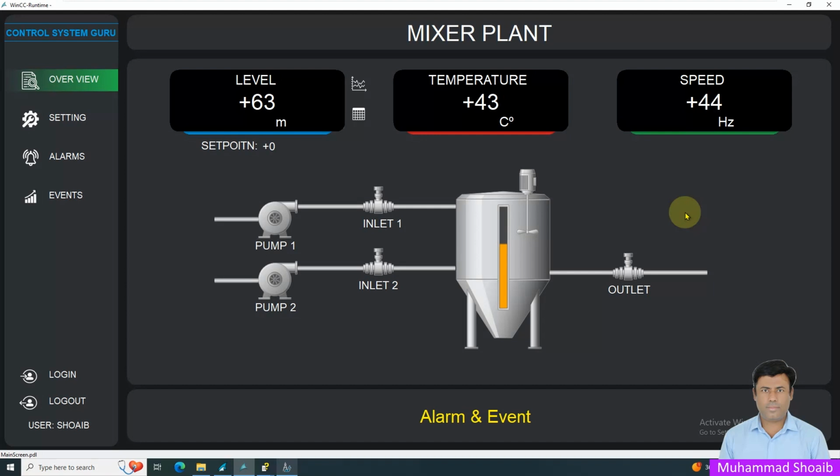In WinCC, cyclic selective acquisition allows you to archive data based on a specific condition such as an alarm, user actions, or external triggers. When the start event occurs, data is logged at regular intervals until the event is cleared or the stop condition is met.